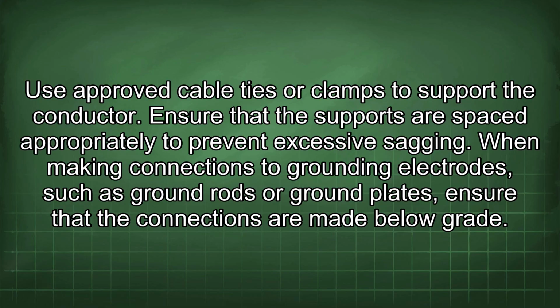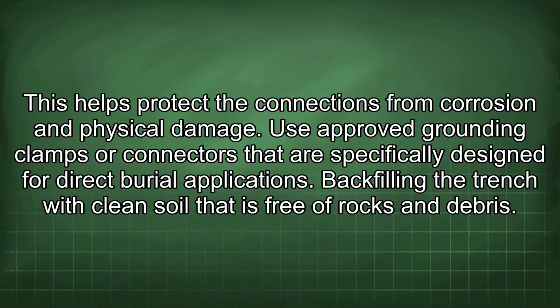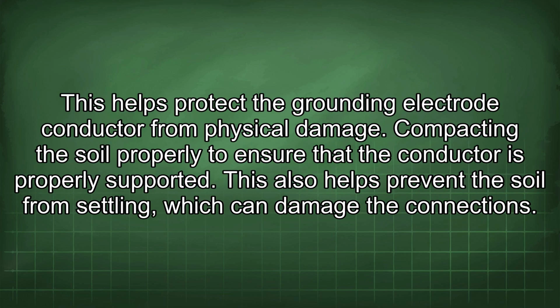When making connections to grounding electrodes, such as ground rods or ground plates, ensure that the connections are made below grade. This helps protect the connections from corrosion and physical damage. Use approved grounding clamps or connectors that are specifically designed for direct burial applications. Backfill the trench with clean soil that is free of rocks and debris. This helps protect the grounding electrode conductor from physical damage.